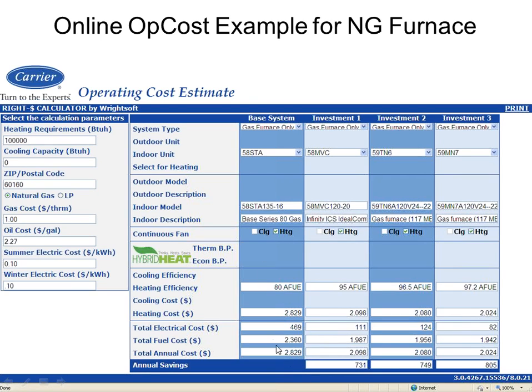So here's the basic furnace they could buy at a legal minimum. This guy saves $800 over that, which is a great story. However, he only saves $50 over one of these other 2 or 3 stage furnaces. So having a modulating furnace is not going to save you a ton of energy. I mean, it's going to save you a ton of energy compared to whatever crappy thing you have now, but comparing the modulating furnace to other premium 2 and 3 stage units, it's pretty close.